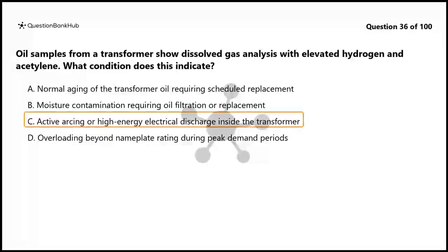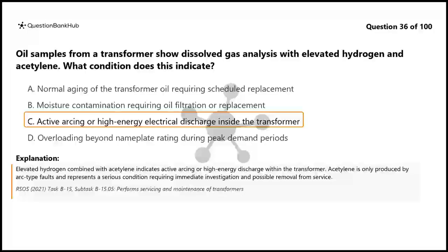The correct answer is C. Active arcing or high-energy electrical discharge inside the transformer. Elevated hydrogen combined with acetylene indicates active arcing or high-energy discharge within the transformer. Acetylene is only produced by arc-type faults and represents a serious condition requiring immediate investigation and possible removal from service.